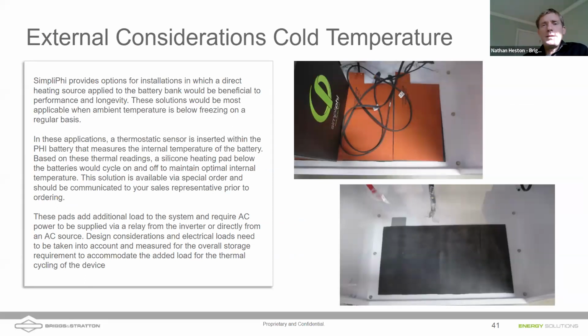If you're installing in cold environments and installing outdoors, you might also be interested in having some temperature control. We have a somewhat unique heating pad design that is built in the factory. This is a special order item, but if you know you're going to be installing batteries in a cold environment, you might want to order them with these heating pads. These heating pads are temperature controlled, so if the battery temperature gets below freezing, which is dangerous for lithium batteries, especially in the charge cycle, the heating pads will come on and draw a little bit of power. I think it's 120 watts out of the battery to warm up those batteries, and then the charging cycle can commence without any damage to the batteries. So if you're interested in this type of solution, it's something that we offer.